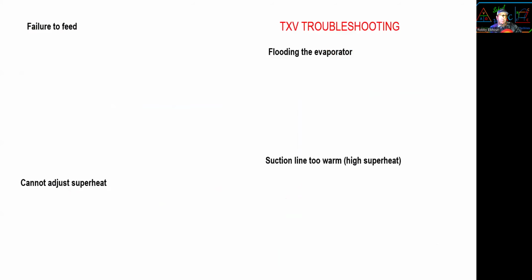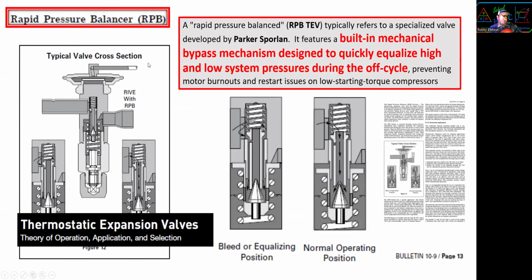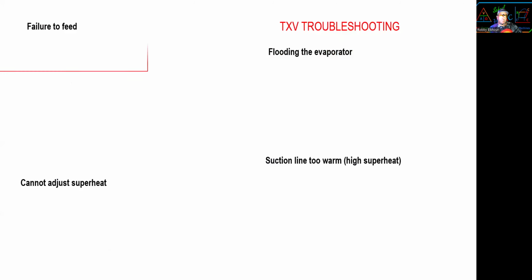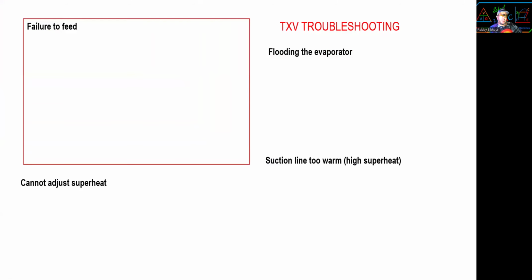Alrighty. Now for this, this one is the rapid pressure balance TXV, which is designed to quickly equalize the high side into the low side during the off cycle. That's for air conditioners. So when the AC shuts off, you want the pressure to equalize. All right, now troubleshooting, failure to feed.